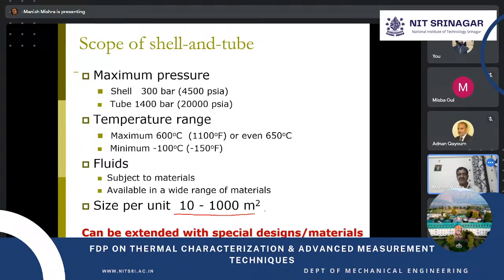But when it is only the heat transfer area, we may not be able to imagine it properly. So it is basically the surface area density. Going back, it is of the order of 60, 100, and so on, meter square per meter cube. Up to 100, you can say the shell and tube heat exchanger construction comes with this area density.